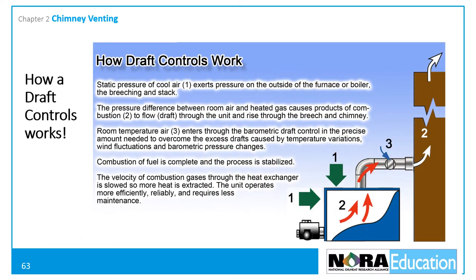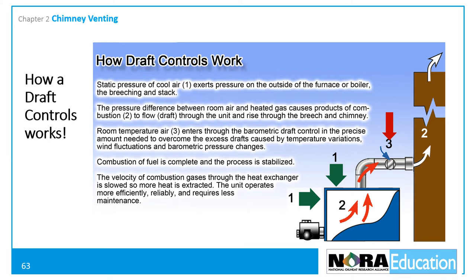This illustration shows the operation of a draft control. The static pressure of cool air exerts pressure on the outside of the appliance, the breaching, and the flue pipe. The pressure difference between room air and combustion gases causes the gases to flow through the appliance and rise through the flue and chimney. Room-temperature air enters through the draft regulator in the precise amount needed to overcome excess draft caused by temperature variations, wind fluctuations, and barometric pressure changes. The result is that the velocity of combustion gases through the heat exchanger is slowed, more heat is extracted, and the unit operates more efficiently, more reliably, and requires less maintenance.